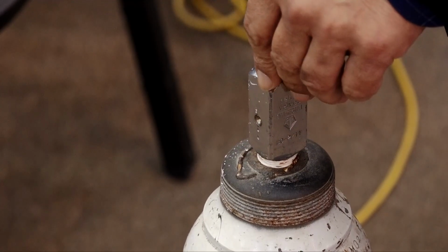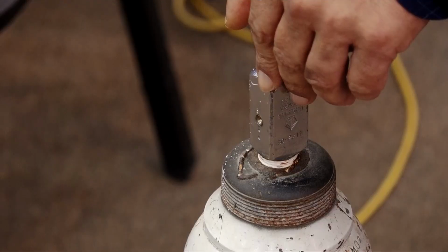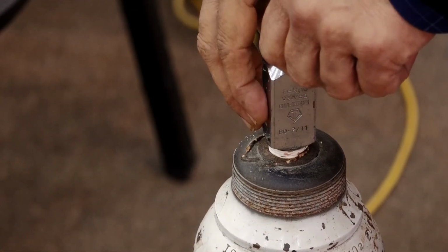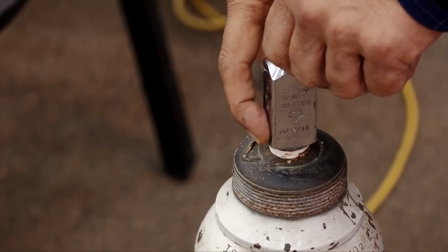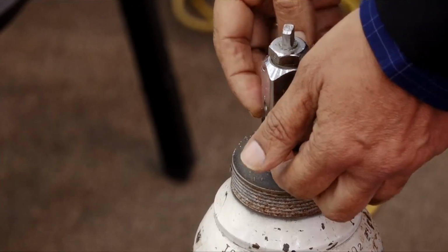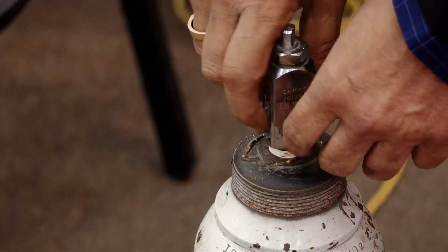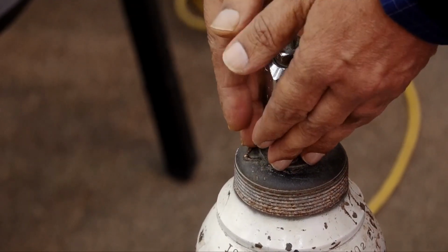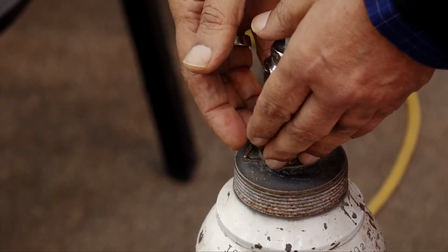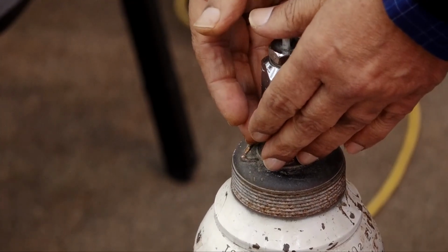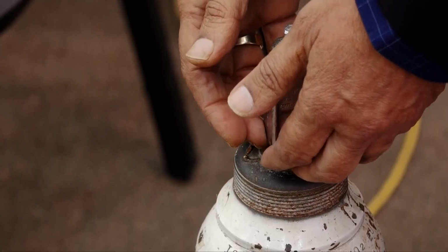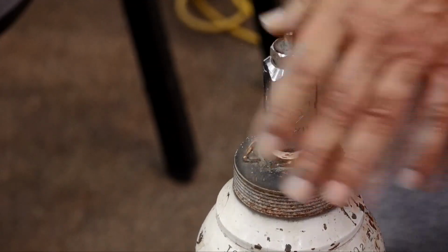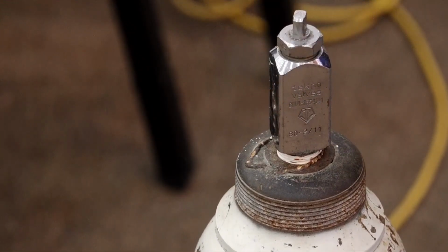But unfortunately, in Indian cylinders, we don't have a pressure relief device under the conical depression. You will be asked again in the exam, where is the pressure relief device? You will be searching underneath the conical depression, but it is not there. Actually, where the cylinder valve is screwed into the main cylinder body, in between, Wood's metal has been kept. Whenever the temperature increases, this Wood's metal will melt and give vent to the gases. That is how explosion is prevented.